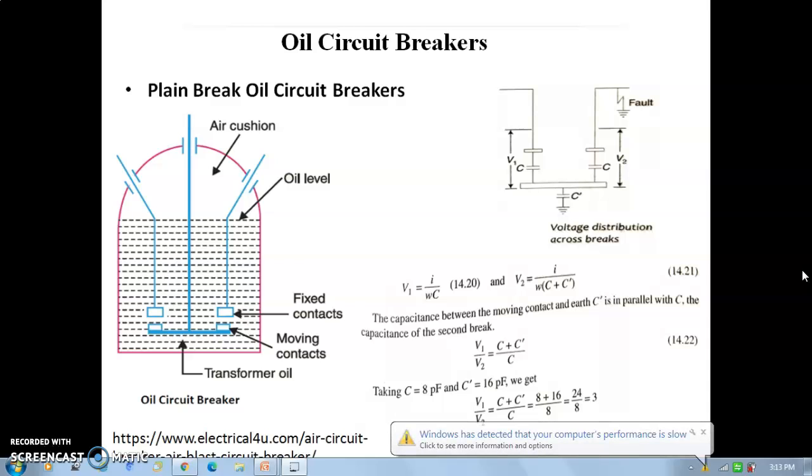When a fault occurs, the circuit breaker contacts open in oil so that an arc is struck between them. Due to the heat of the arc, the surrounding oil of the contacts evaporates and hydrogen gas is produced at higher pressure. The oil is pushed away from the arc and hydrogen gas bubbles surround the arc, so that the adjacent portion of the contacts are surrounded by bubbles.